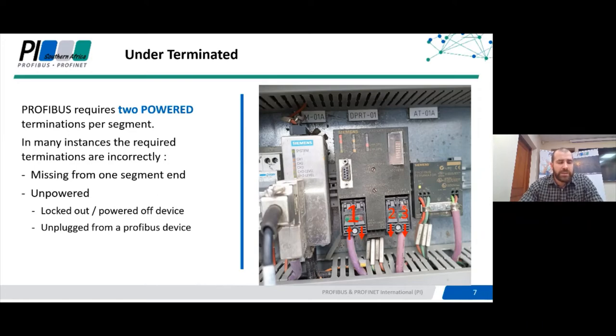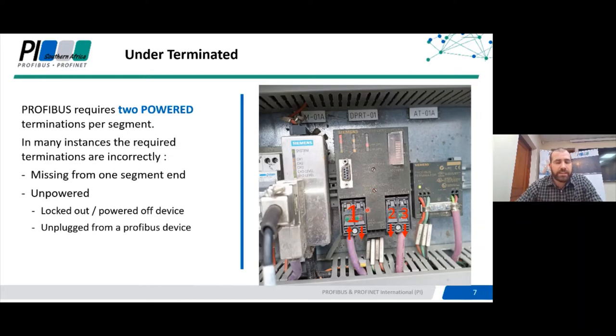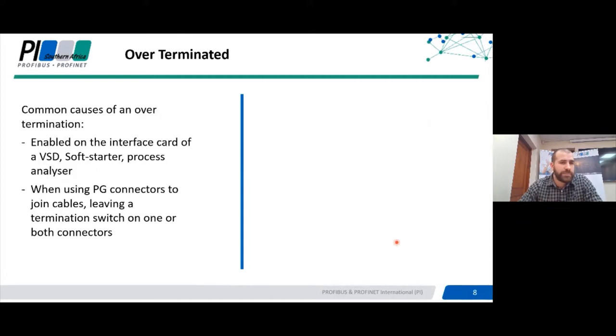The two other ports are automatically terminated because they're the beginning of the next two segments. If you look at the switch, it's indicating that the termination on DP1 is off, which means there is actually an under-termination in this scenario — so that is something to keep an eye out for. The other switch allows you to disable segment three if it's not being used; sometimes you can use this device just by enabling segment two.